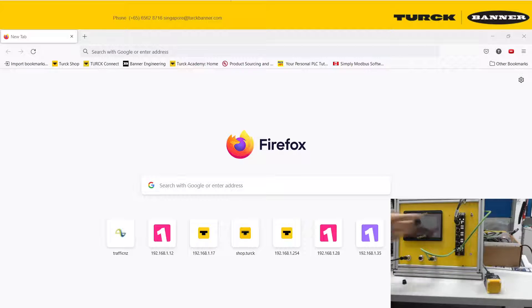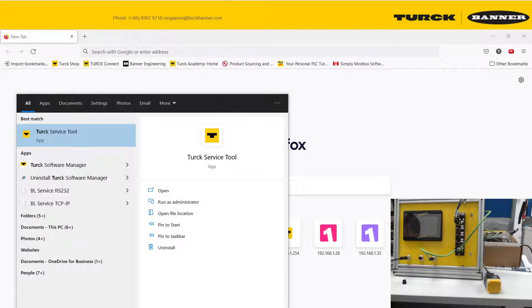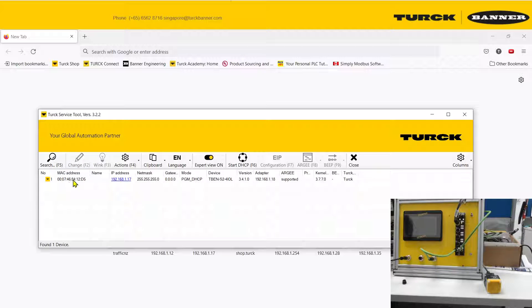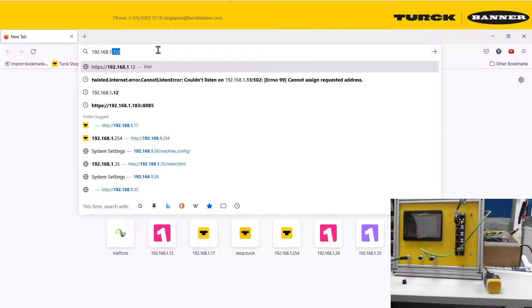First of all, we're going to log in to the TBEN-S2-4IOL. The first thing you will need is the IP address. If you know your IP address, that is good. If you forgot, you can use the Turck service tool, which can be downloaded over the internet. Search for devices connected to your computer, and you can see the device is found with its IP address. You can then key the IP address into your web browser.